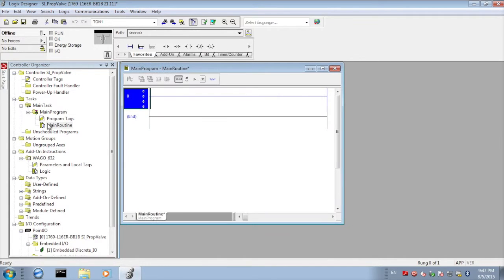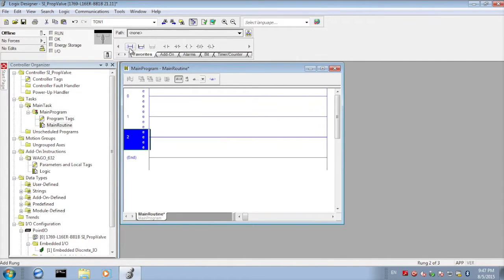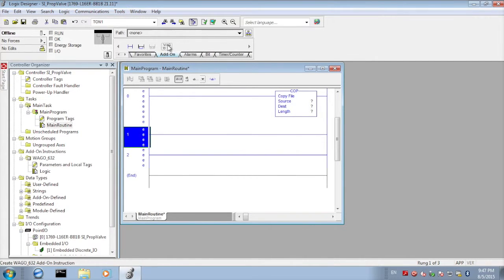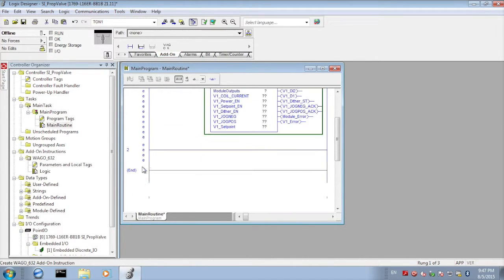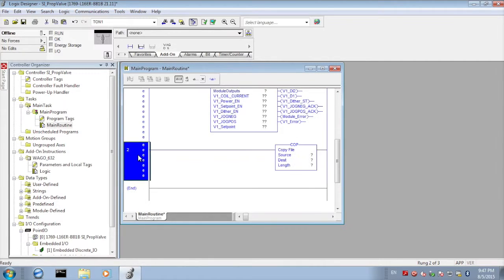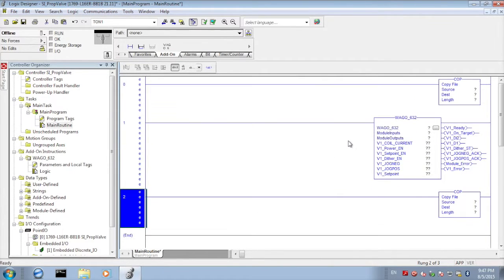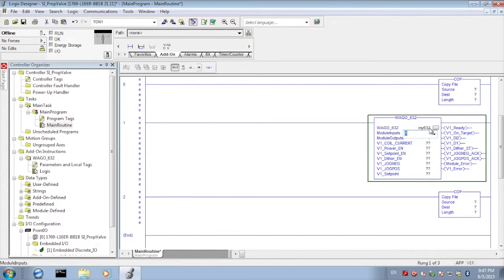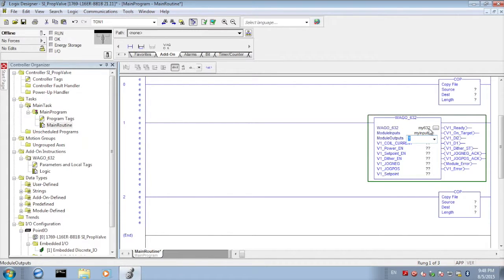So in our main routine it's very simple, we're going to have three rungs of ladder logic. The first one is going to be a copy function. The next is going to be our add-on instruction. The third one is also going to be a copy. Essentially we're going to copy data into the add-on instruction and then copy it out. We'll create the instance of the add-on instruction and call it my632.